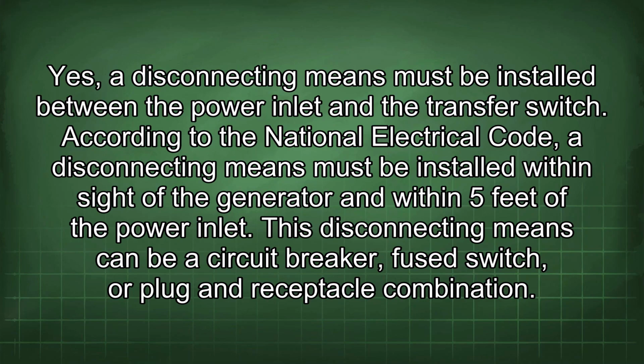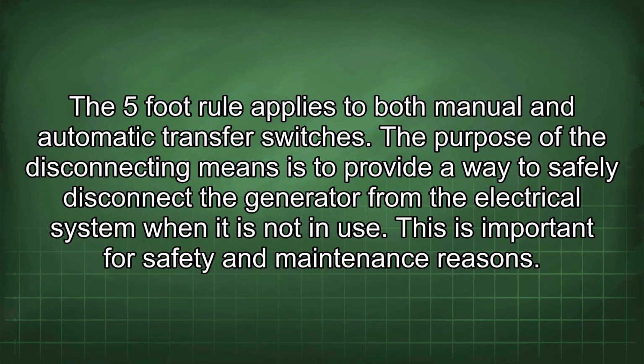Yes, a disconnecting means must be installed between the power inlet and the transfer switch. According to the National Electrical Code, a disconnecting means must be installed within sight of the generator and within 5 feet of the power inlet. This disconnecting means can be a circuit breaker, fuse switch, or plug and receptacle combination. The 5-foot rule applies to both manual and automatic transfer switches.